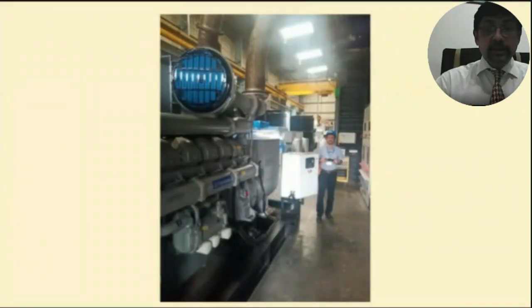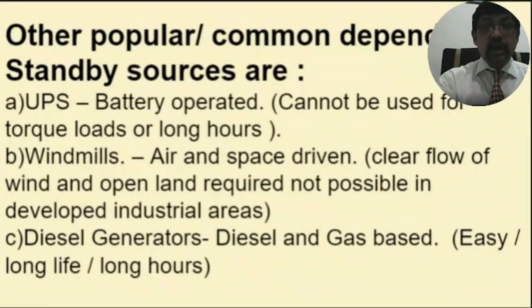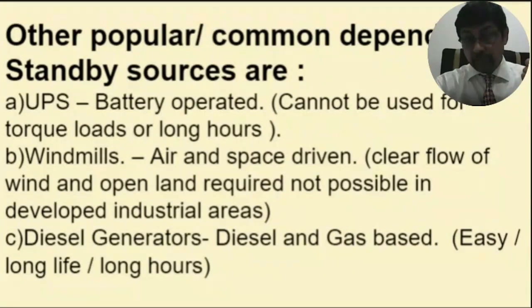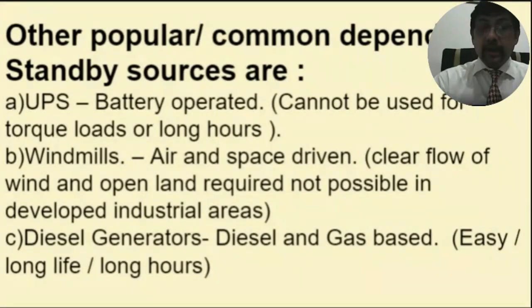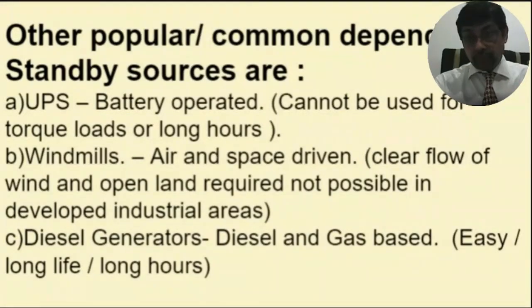The other dependable sources, apart from the grid: suppose the grid is not sufficient to give us the required power, the standby power on which we can depend, most commonly used, is the UPS. UPS is uninterrupted power source. It is battery operated, with a battery backup system. The only thing is that it cannot be used for long hours, probably 5 to 6 hours maximum. At the same time, it cannot take care of the torque load. When a machine, the AC or bigger motors start, the UPS cannot take care of that kind of torque load. Torque load is, you know.